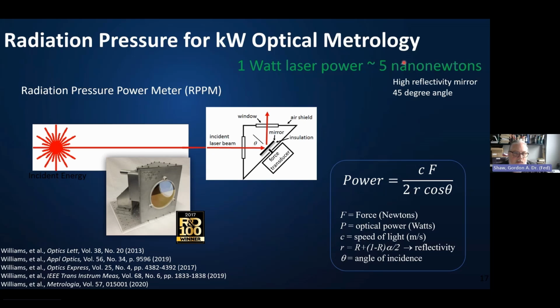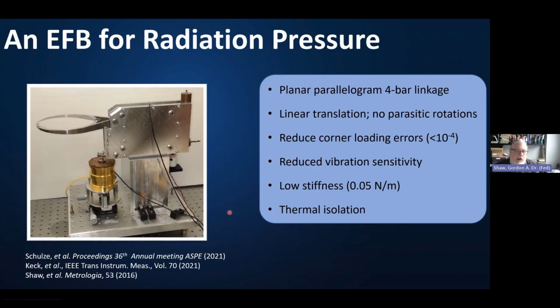And in this case, at this 45-degree angle with a high reflectivity mirror, we get about 5 nanonewtons of force from 1 watt of laser power. And there is a NIST reference device called the radiation pressure power meter that does this, but we calibrate this with masses that are measured on the electrostatic force balance. But we thought it would be cleaner if we could provide a direct traceability pathway to the fundamental constants using a balance to directly measure the radiation pressure force.